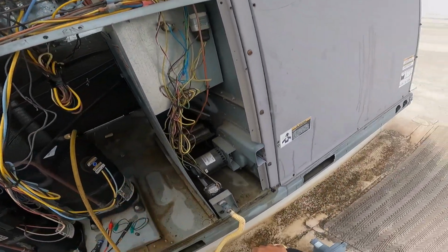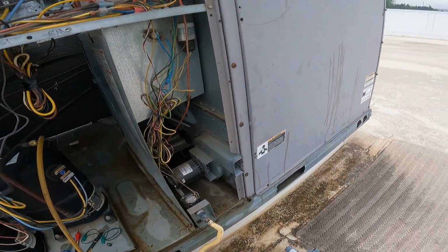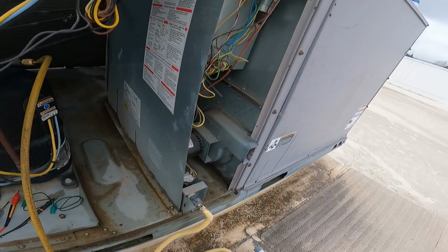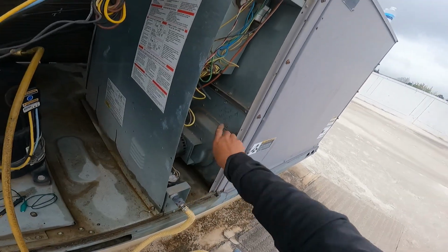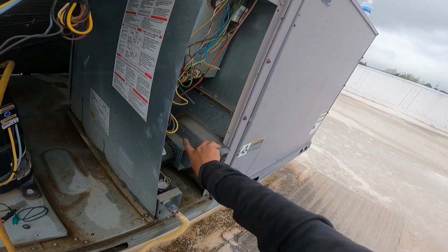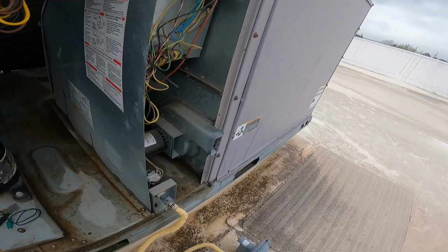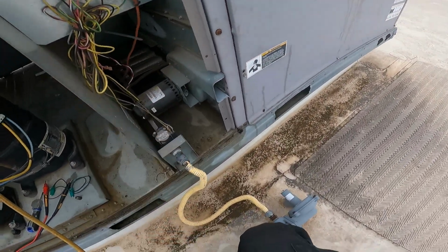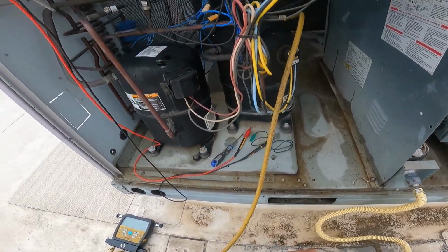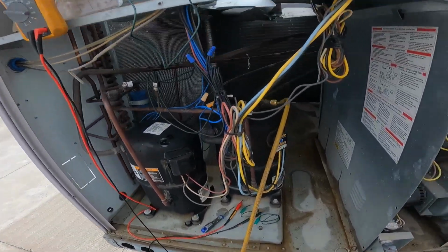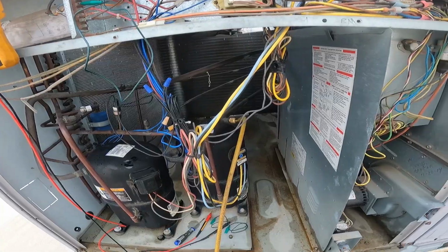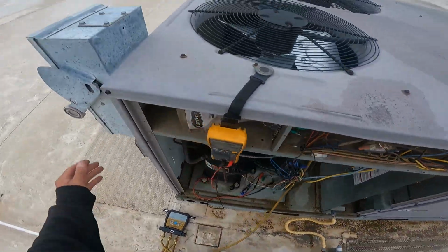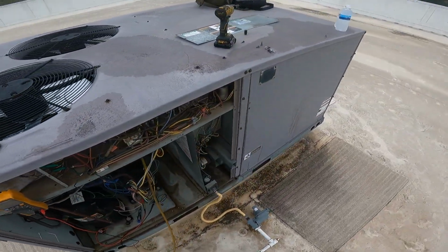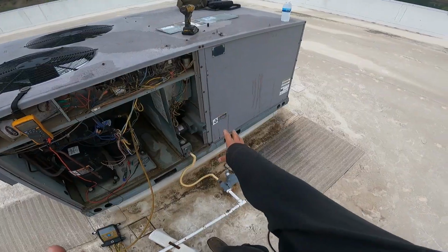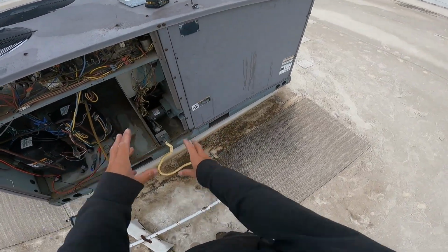We're going to see if this thing fires off. If it does, we can go ahead and say that, look, in 2014 they replaced this - wow, 10 years ago they replaced that inducer motor. That was just like yesterday. So anyhow, without further ado, let's see if it fires off. Inducer works, spark, flame.